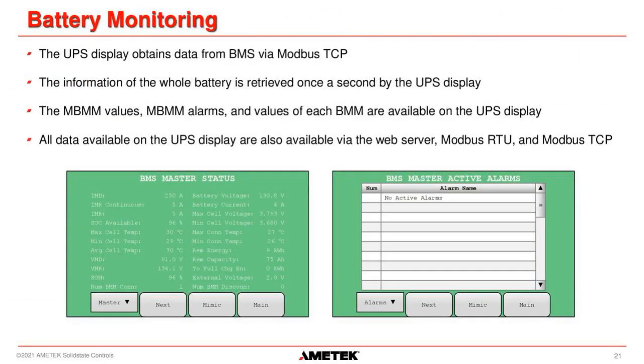So these are the new HMI screens that we have for lithium-ion batteries. The UPS obtains these values from the battery using Modbus TCP. The information of the whole battery string is retrieved once a second by the UPS, but you can have multiple cabinets in a string, so those values from each cabinet are pulled every 7 seconds.